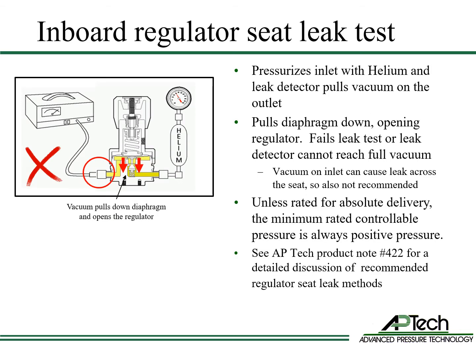The helium inboard seat leak test is not recommended for regulators because, unless you're using a sub-atmospheric regulator, pulling vacuum on the outlet of the regulator will often open the regulator, breaking the seat seal and exposing the low pressure side to pressurized helium. Vacuum on the inlet is also not recommended because it can cause a leak across the seat. A regulator does have a vacuum inlet pressure rating, but it is intended for purging, inboard testing, and system flush down only. Unless the regulator is rated for absolute delivery, the minimum rated controllable outlet pressure is always a positive pressure, typically 1 psig or greater. For more detailed information and discussion of recommended regulator seat leak test methods, please see product note number 422.